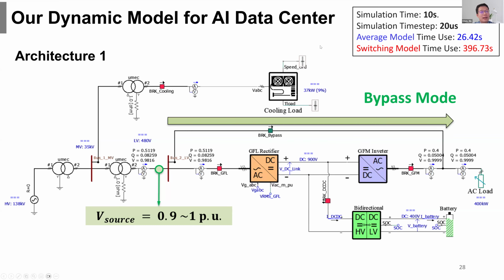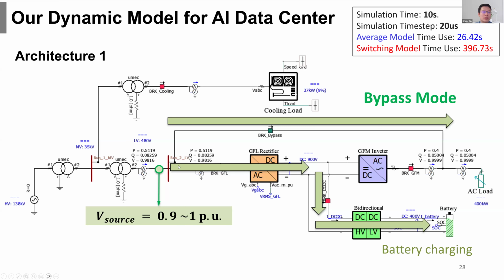And in this case, the data center will operate in the bypass mode. That means the power is directly going through this bypass switch to supply the AC computing load. It's not going through the rectifier and the inverter. And also in this case, we can use the rectifier and DC-DC converter to charge the battery if needed.